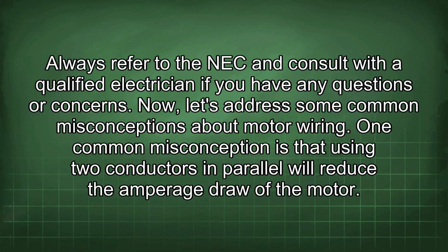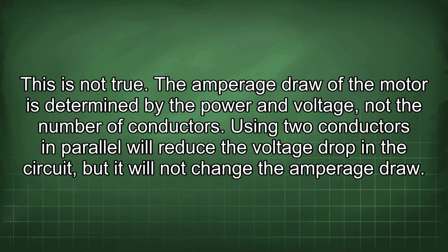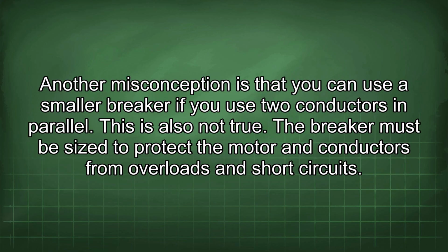Now, let's address some common misconceptions about motor wiring. One common misconception is that using two conductors in parallel will reduce the amperage draw of the motor. This is not true. The amperage draw of the motor is determined by the power and voltage, not the number of conductors. Using two conductors in parallel will reduce the voltage drop in the circuit, but it will not change the amperage draw. Another misconception is that you can use a smaller breaker if you use two conductors in parallel. This is also not true.